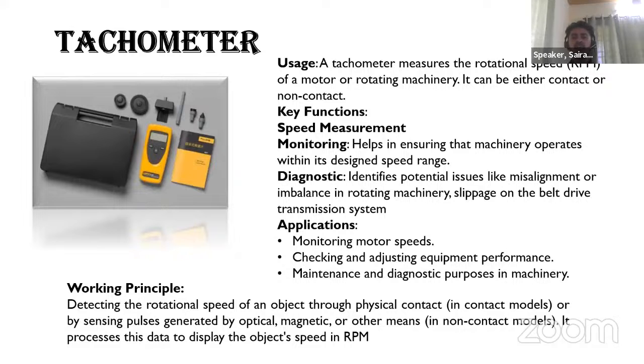Tachometer. This tachometer is used for measuring the RPM of the driver pulley and driven pulley for measuring the slip. It has both contact and non-contact types, which are used for measuring the motor speed, so that we can directly get the slip percentage of the motors, and we can take corrective actions if the slip is getting to the higher side. This works on the principle of physical contact in the contact mode, and for the non-contact mode, it works with optical or magnetic means.